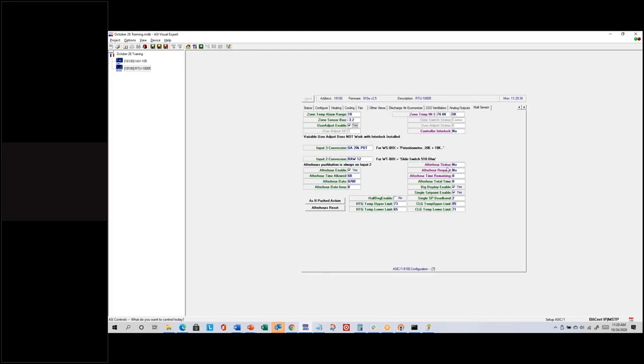The wall sensor settings are in a slightly different spot but functionally the same. I can enable set point adjustment and the digital display with the WSO61. I can set the single set point so the WSO61 changes heating and cooling set points simultaneously by adjusting the midpoint. With after hours enable, I can set how many minutes of occupancy they get when they push the button.